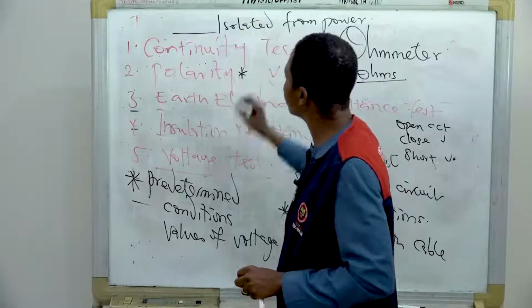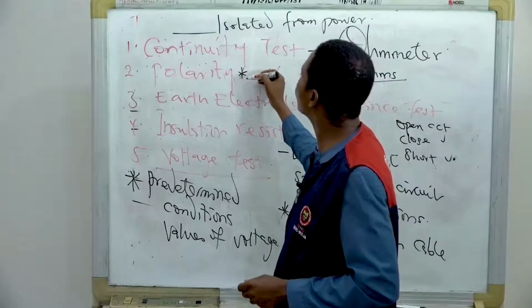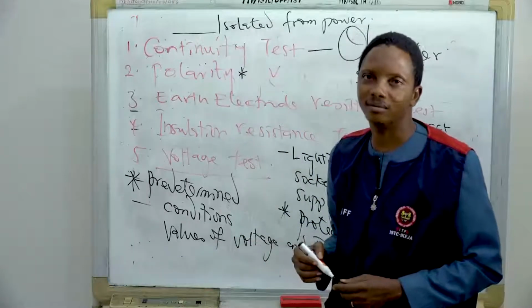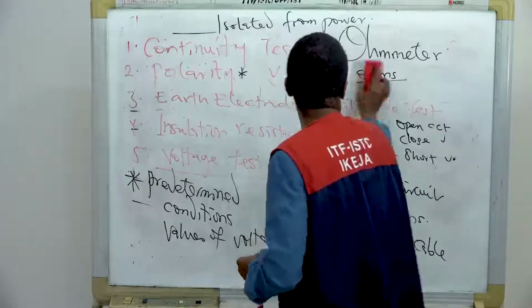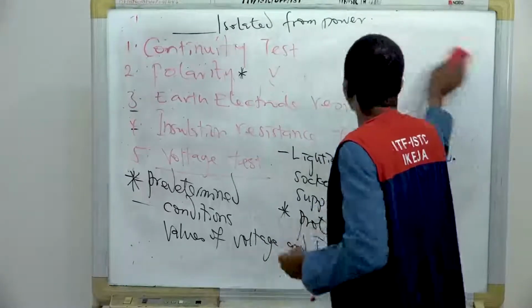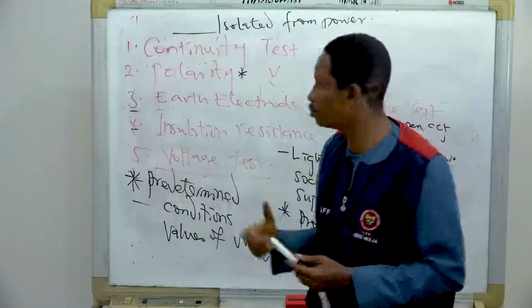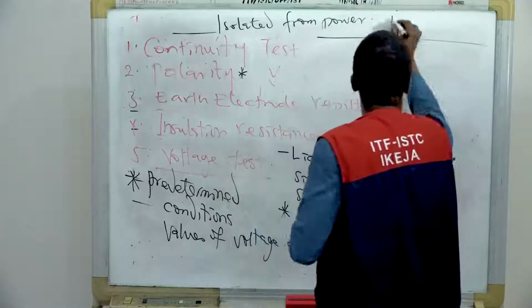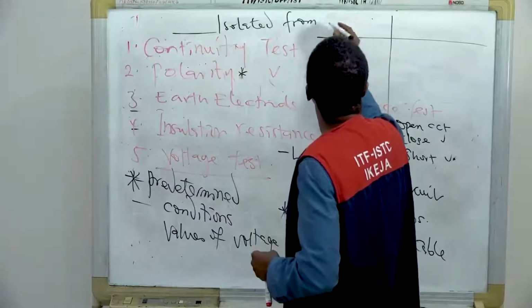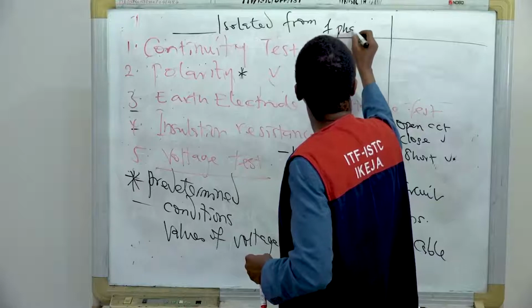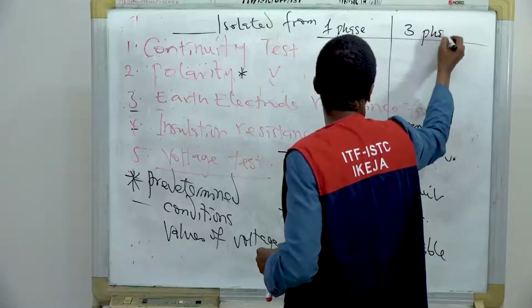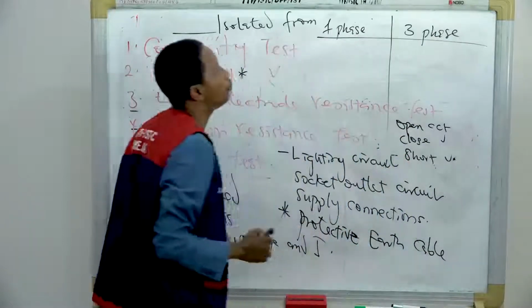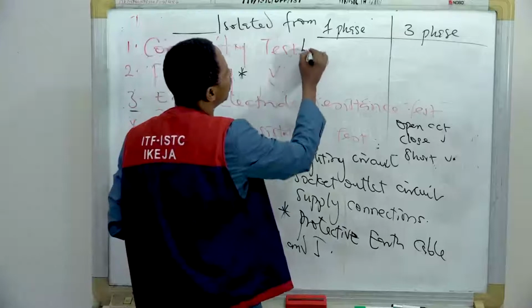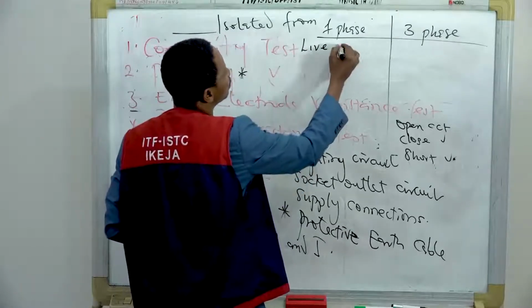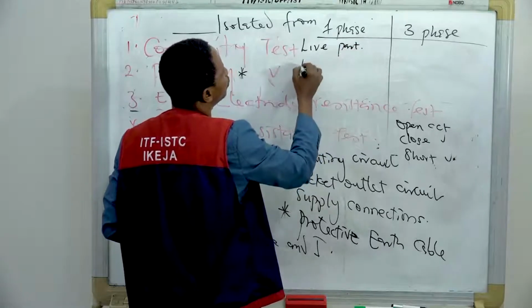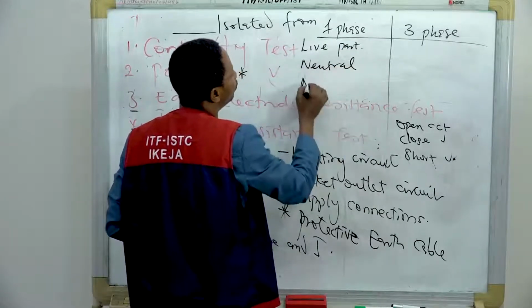Now, talking about polarity test. For polarity test, we are also using ohmmeter to carry out our polarity test, to determine something. And what do we want to determine? We are determining two things. Number one, if the circuit is single phase or three phase. Now, polarity. For single phase, we have the live conductor, and we have the neutral, and we have the earth.